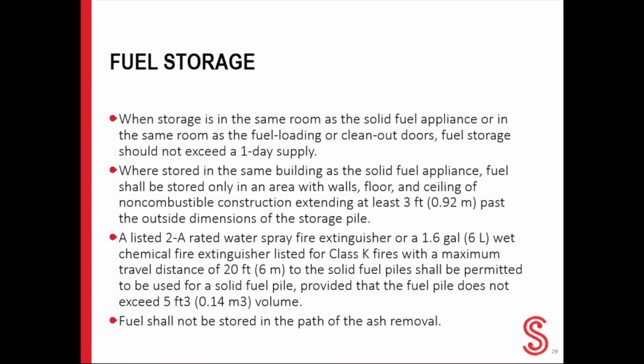Talking about fuel storage now, obviously most of these solid fuel cooking appliances require some sort of fuel. So only 1 day's supply of fuel should be kept in the same room as the solid fuel cooking appliance per NFPA 96, Chapter 14. Solid fuel should not be stored within 3 feet of any cooking appliance. Both of these rules are to reduce possible fire hazards due to sparks generated from burning solid fuel.